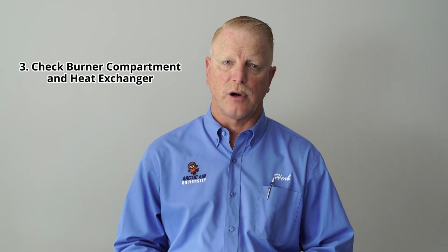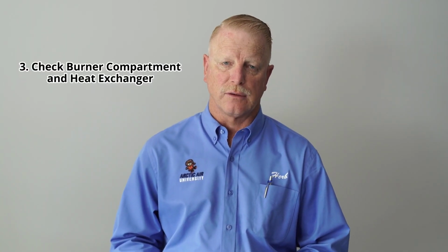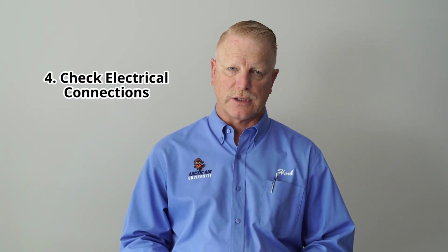Second and most important, we will be cleaning your flame sensor. Every modern day furnace that is out there now, the last 20 years, has a flame sensor and must be cleaned annually before the heating season. Next, we're going to check your burner compartment and your heat exchanger, make sure the integrity is well on all that, and clean them and brush them out and vacuum it if necessary. Next, after that, we'll check all your electrical connections from low voltage to high voltage and check all your safeties and make sure they are in proper order.